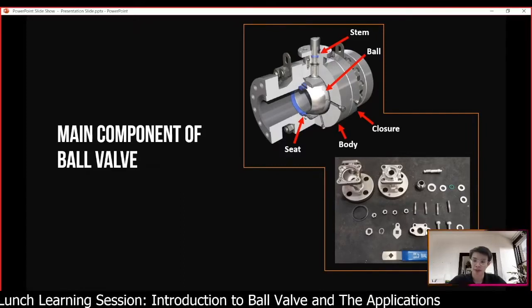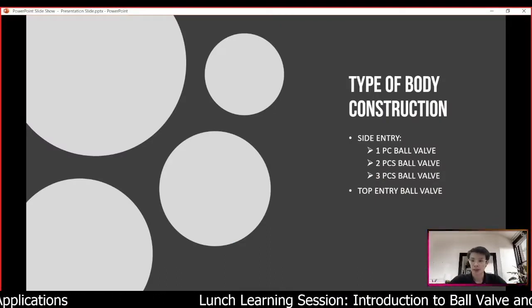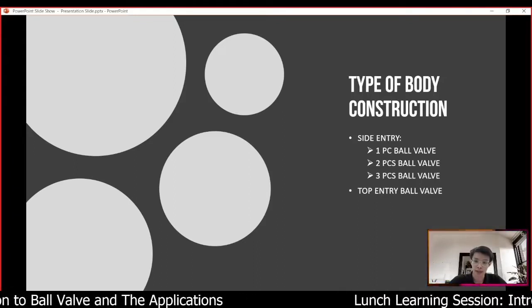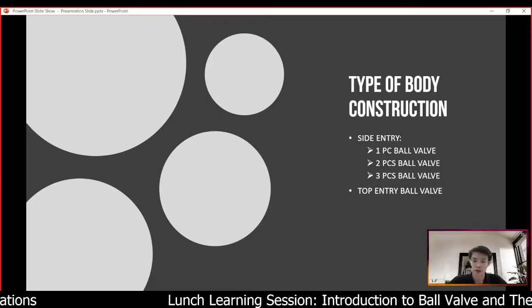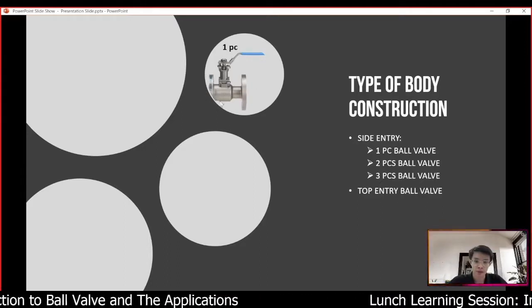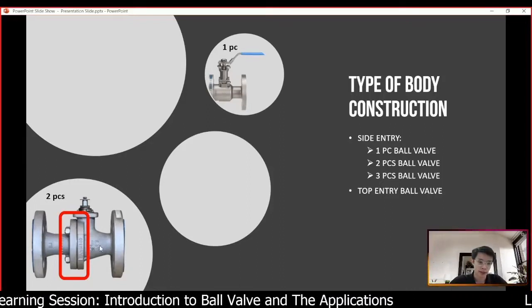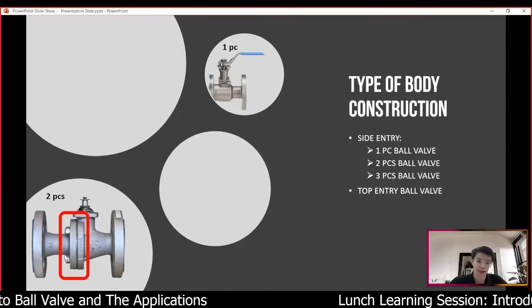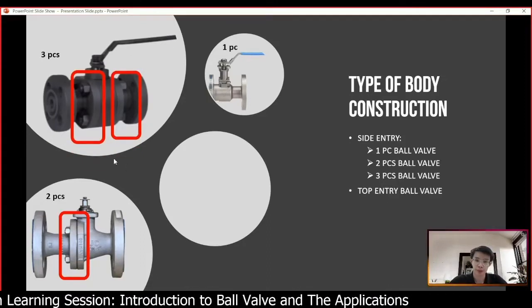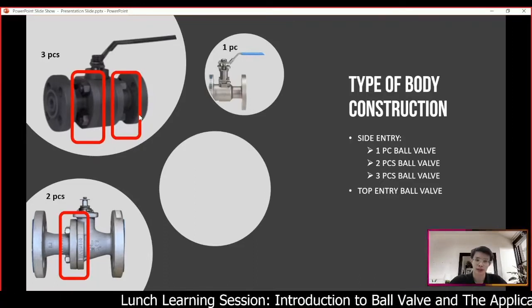Next, type of body construction. For ball valves they can be categorized into side entry and top entry. For side entry it can be further classified into one piece, two piece, or three piece. A one piece ball valve has a body made from one complete piece. A two piece ball valve has two body pieces — one on the left, one on the right — joined together using stud bolts and nuts. A three piece body is made of three pieces: two closures on the left and right, and the main body at the center.